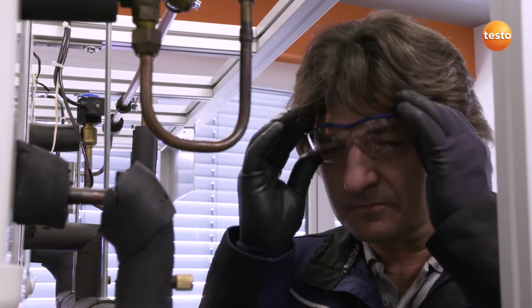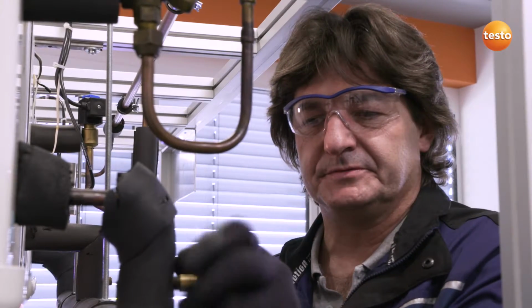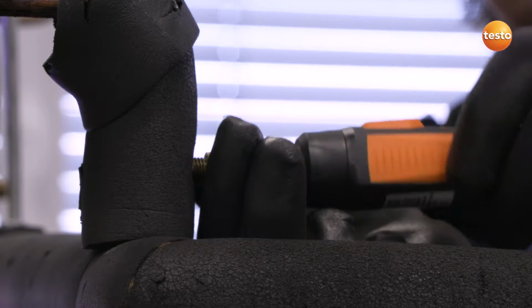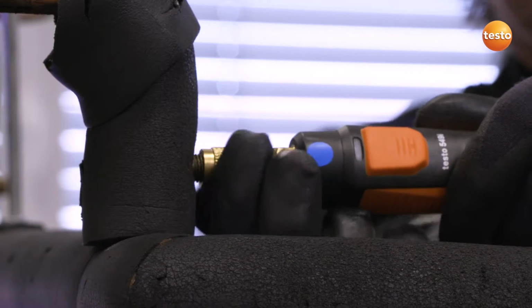At this point, I would like to record the condenser subcooling on this heat exchanger. To do this, I need the pressure and temperature at the condenser outlet. I will connect the pressure sensor to the condenser outlet and firmly attach this to the system.